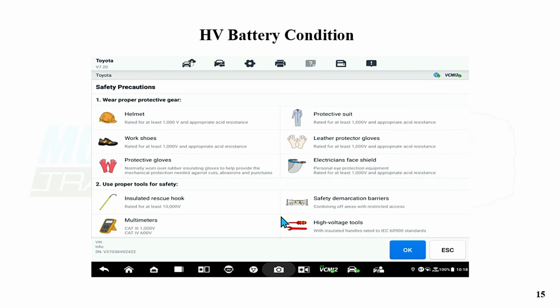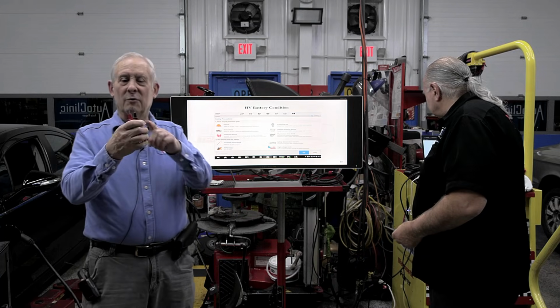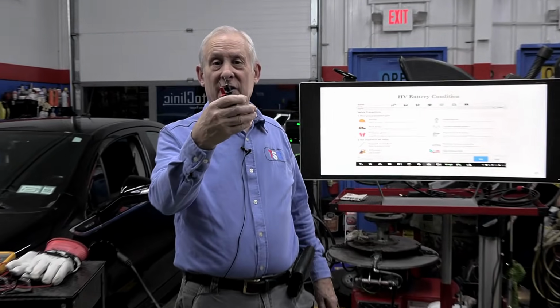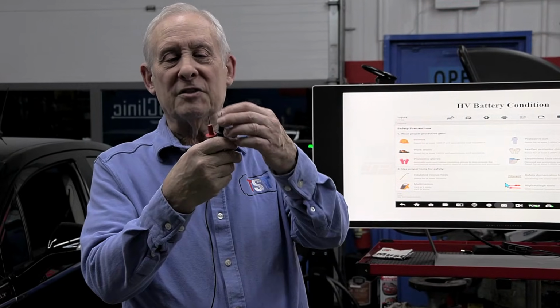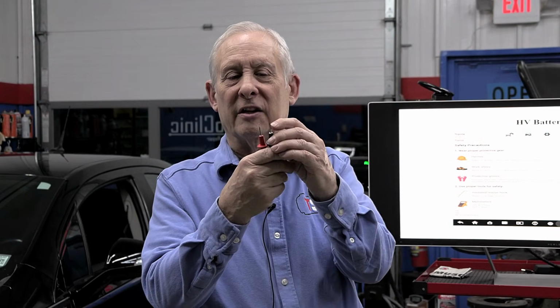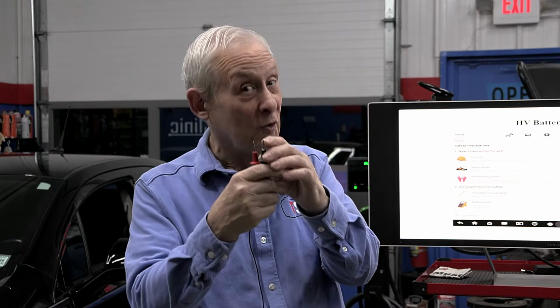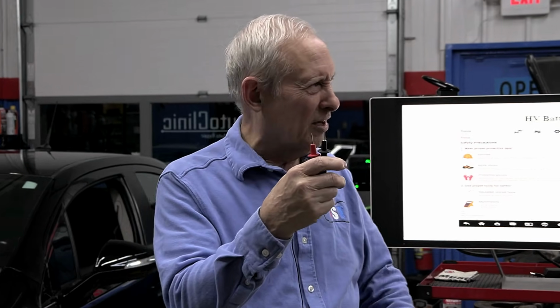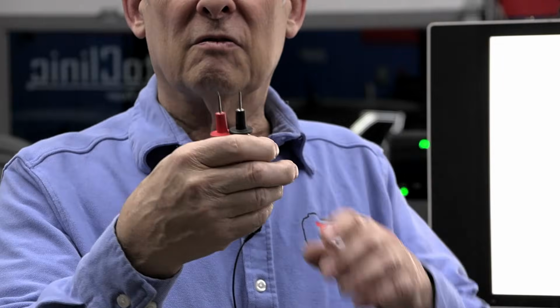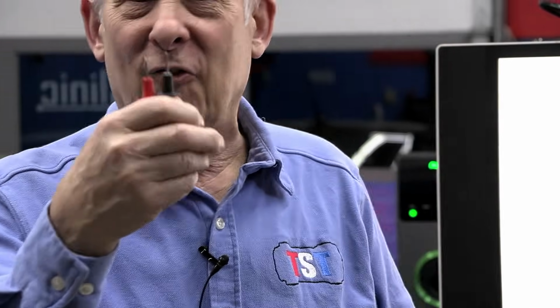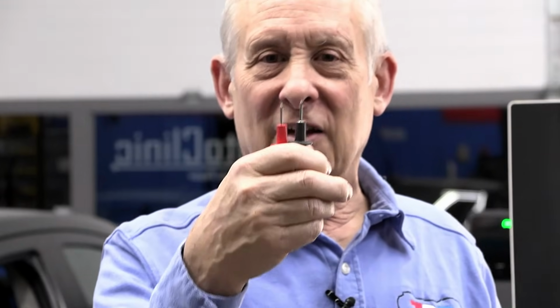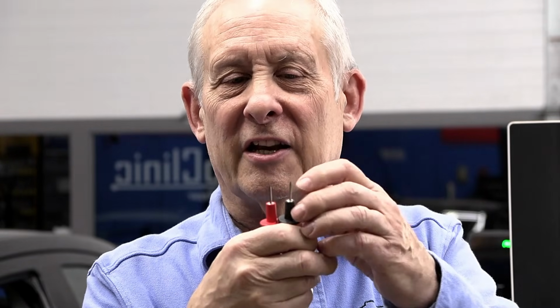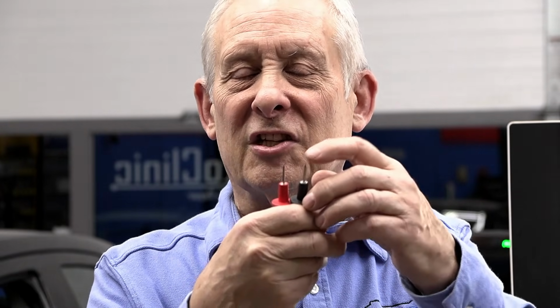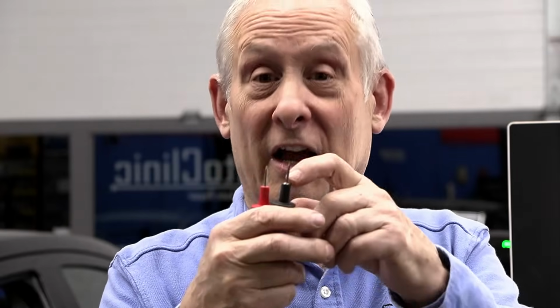Going to show you. These are 1,000 volt rated probes, however they're supposed to have those little collars on them so only the tip sticks out for 1,000 volt usage. Otherwise it's only correct for 600 volts. So that's what it was, it wasn't a faulty part.